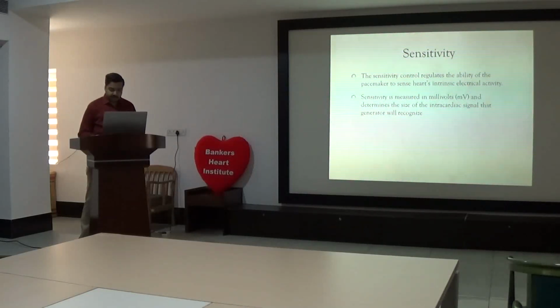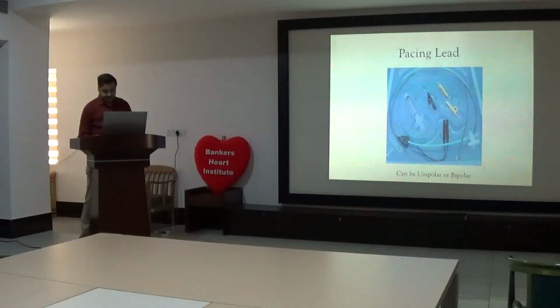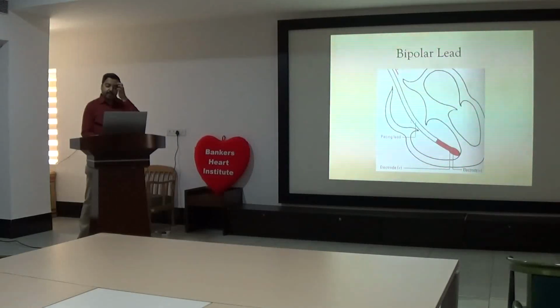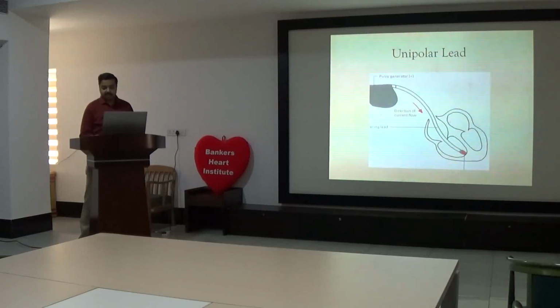This is the pacing lead. There are two kinds of pacing lead. It can be unipolar or bipolar. There will be only one pacing lead, but this is bipolar, where there is one negative electrode and one positive electrode. And versus this, the unipolar lead has only a single negative electrode, and the pulse generator here works as the positive pole. There are no added advantages of unipolar versus bipolar.